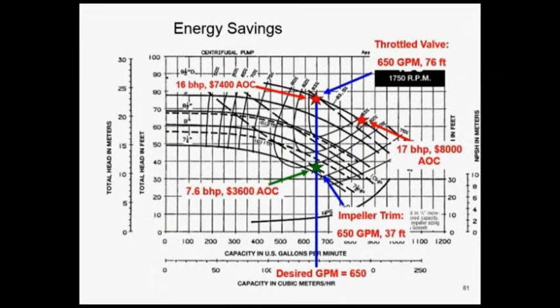When you did the right thing here, you did a proportioning balance. You want to make sure that throttling valve is left wide open, and I trimmed the impeller down or put a variable speed drive on it. I was able to cut the horsepower down to 7.6 brake horsepower, operating cost down to $3,600 a year. I cut it from $8,000 to $3,600 a year, but doing the proper balance, proportion balance versus ASHRAE 90.1 2010 Energy Code, and I still got my 650 GPM. I'm still giving you exactly what you asked for to begin with.